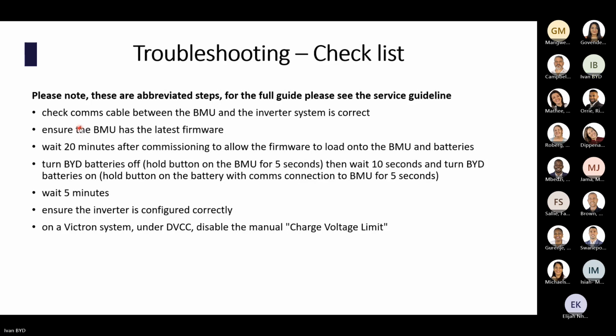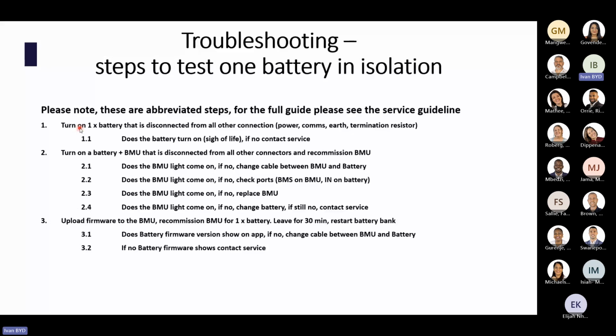And then if there are any issues with the batteries, because all the batteries are modular and you can remove one battery and the rest of the bank can carry on going, you'll have to recommission it for the right number of batteries. And you can test the batteries in isolation if there is an issue with the battery.